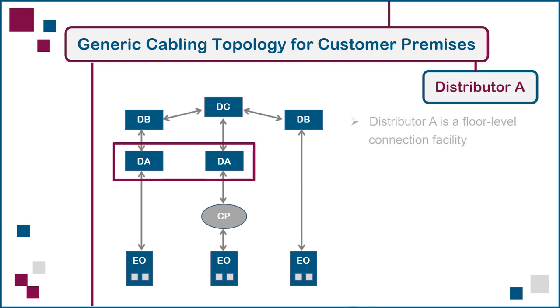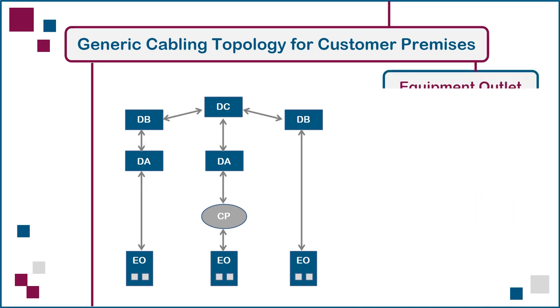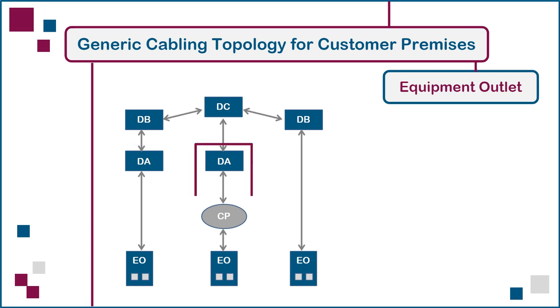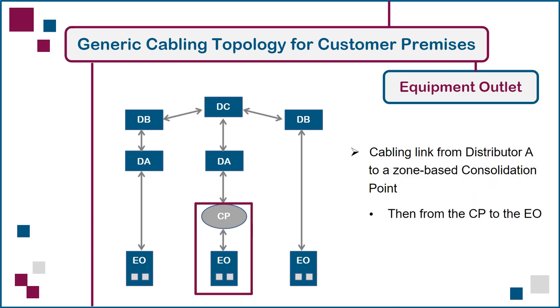Distributor A's are the floor-level connection facilities, located in one or more distributor rooms on each floor of a building. A cabling link from Distributor A can go directly to an equipment outlet or EO, such as a wall-mounted faceplate in an office. Optionally, it can go to a zone-based consolidation point, or CP, along with multiple other cables, and from there to an EO. The consolidation point serves as an additional connector between Distributor A and, for example, equipment outlets within open office modular furniture. Whenever the open office furniture needs to be moved or reconfigured, only the cables from the affected EOs to the nearby CP need to be replaced. The longer cable runs from the CP to Distributor A can remain undisturbed.